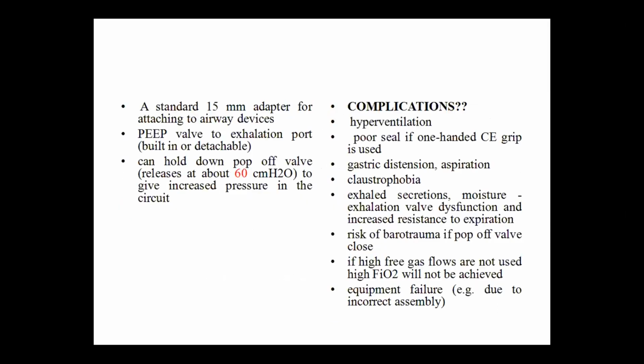As usual, there is a standard 15 mm adapter for attaching to airway devices. The blue valve you see is a pop-off valve, and it manages increased pressure in the circuit. It releases at about 60 centimeters of water, and a PEEP valve can be attached, or sometimes it comes built into the AMBU bag itself.